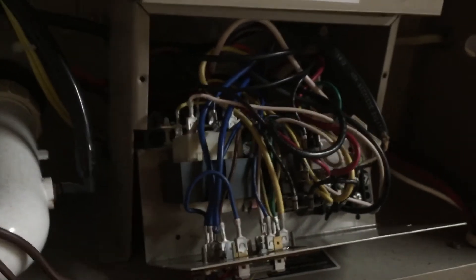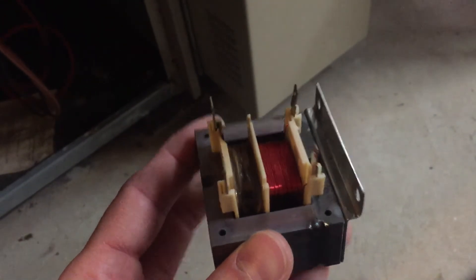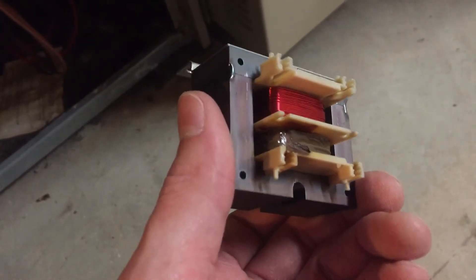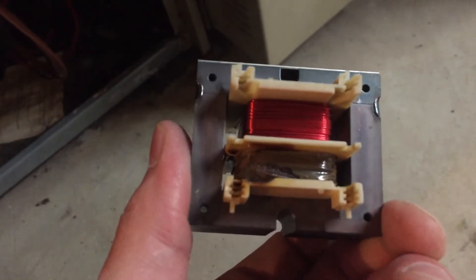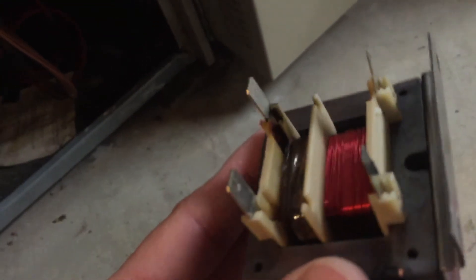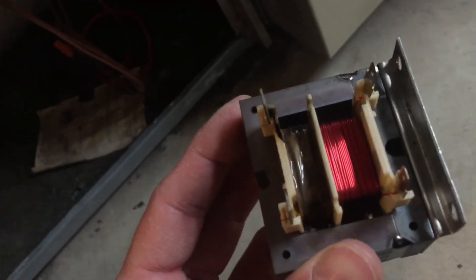So I realized that guy's bad. I pulled it out and took a look at it, and here's the one I pulled out. You can see one side of it is toast — all scorched, burnt, melted plastic going up to that terminal. Just melty plastic and a mess.